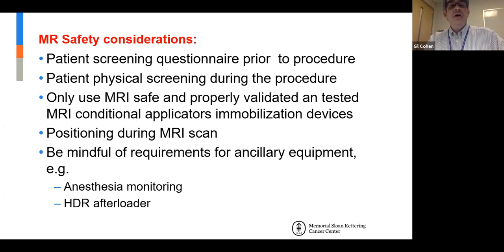We move the patient from our brachy suite to the MRI, and that requires that we make sure nothing foreign, no metallic objects, are brought into the MRI suite. We want to make sure that only MR-safe and properly validated and tested applicators and immobilization devices are brought into the MRI.